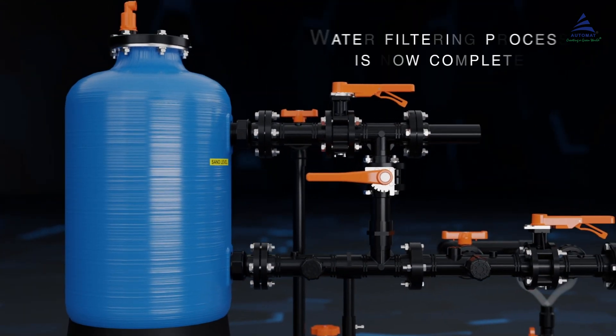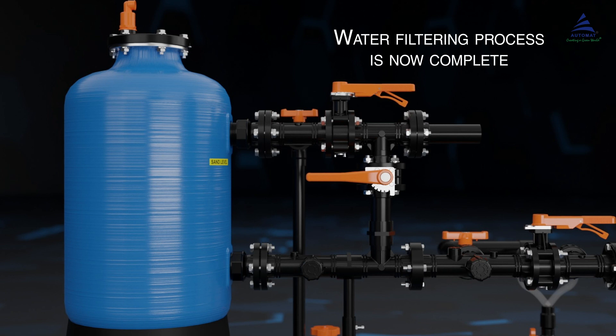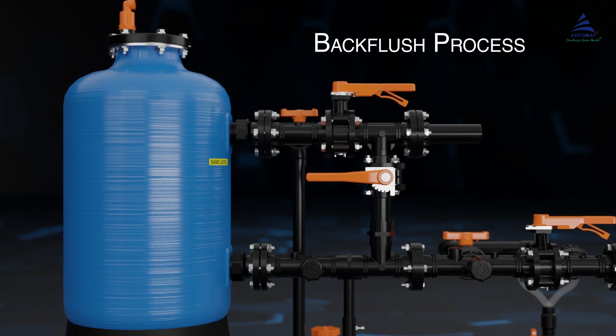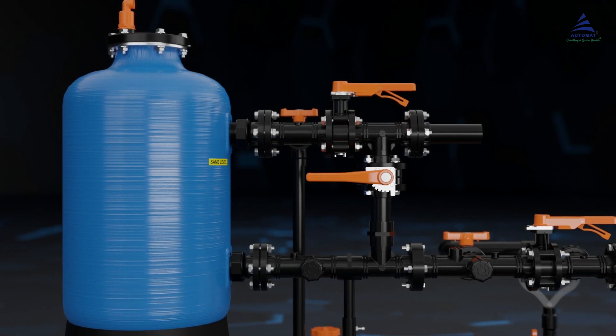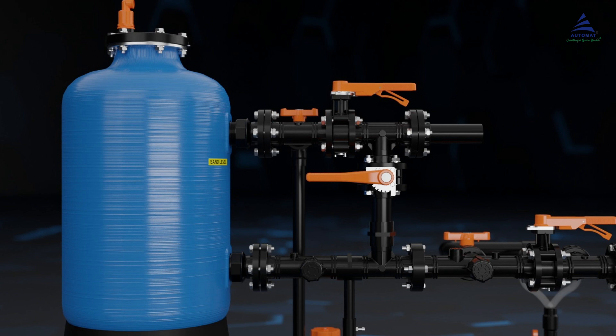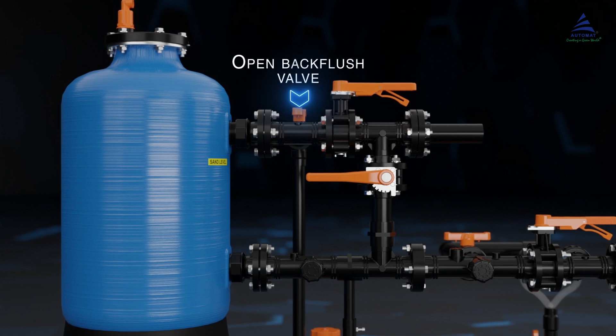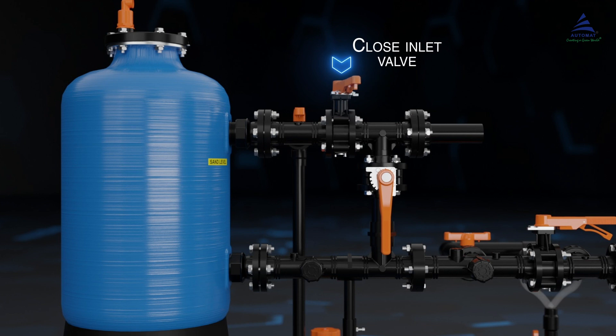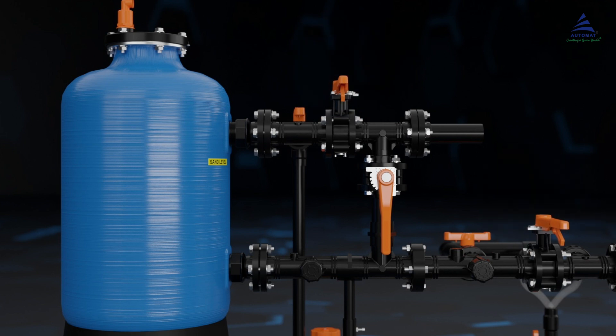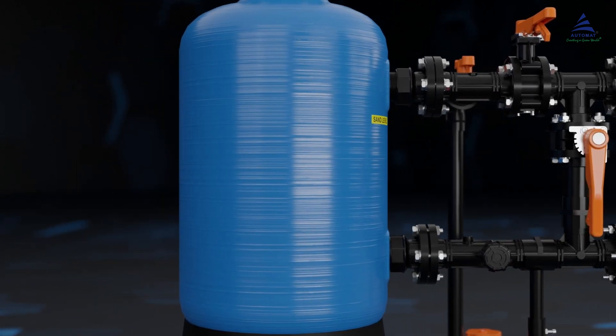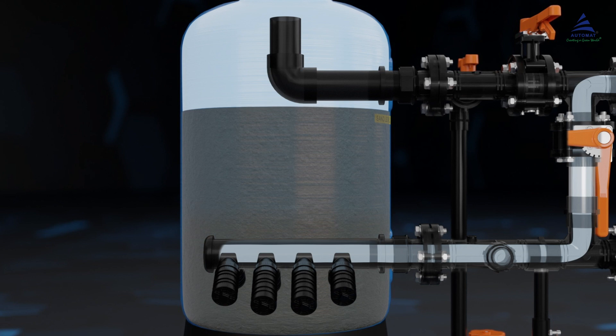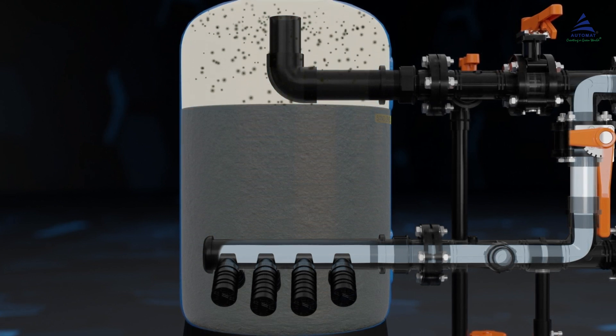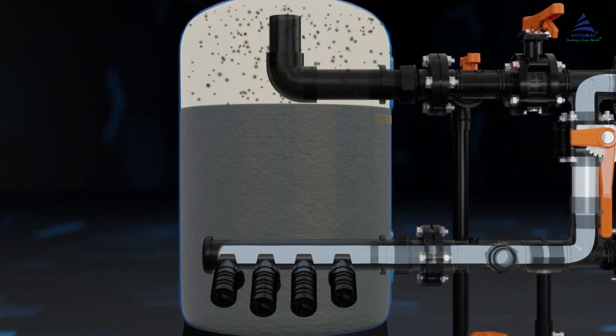Now let us understand the backflush process. In order to start the backflush process, we must simultaneously open the backflush and bypass valves while closing the inlet and outlet valves. Through this process, we clean the sand inside the filter by removing the impurities. The impurities in the tank float above the sand and are discharged through the backflush port.